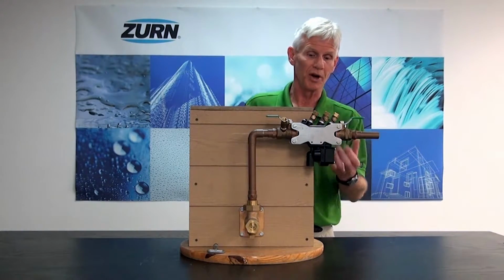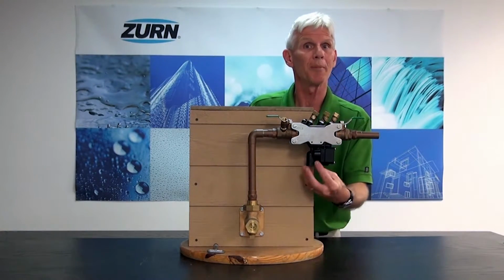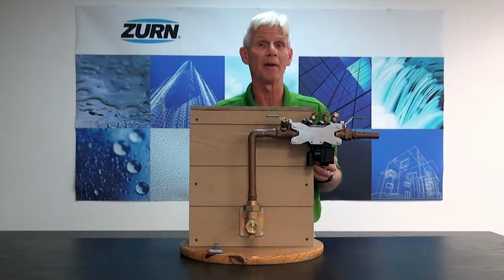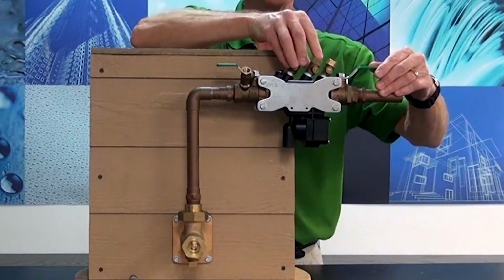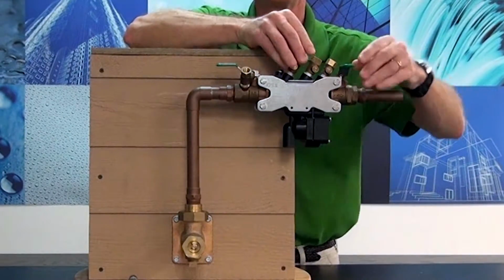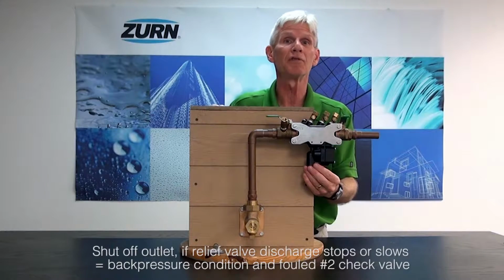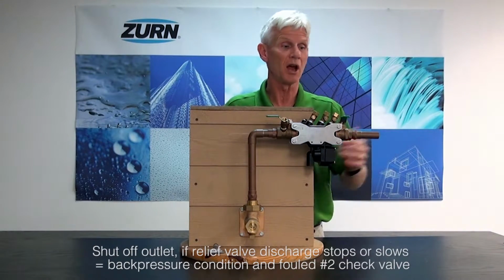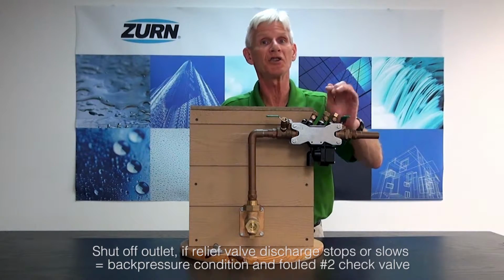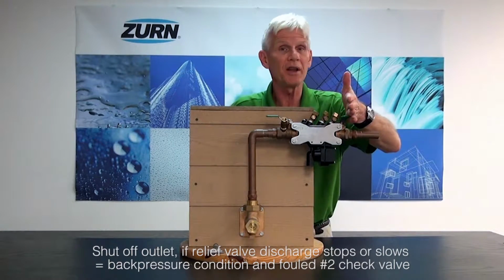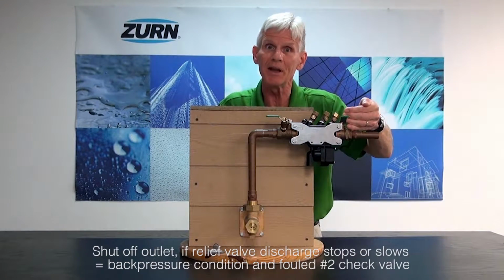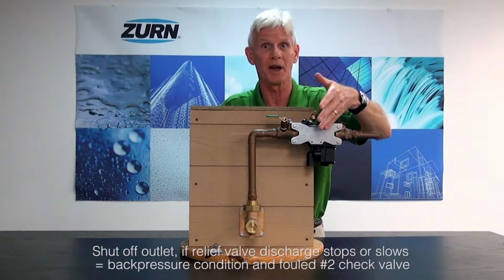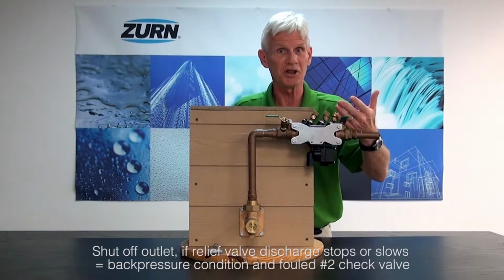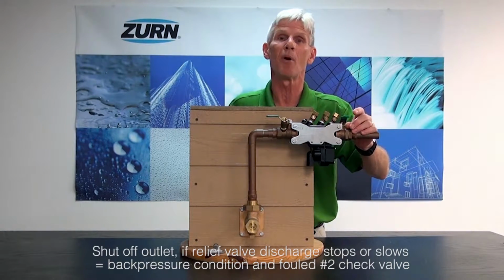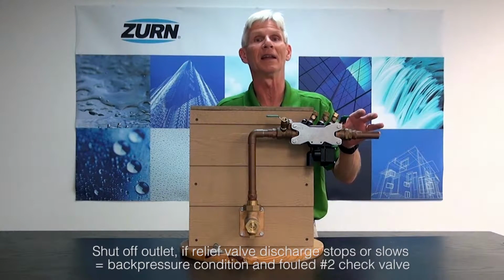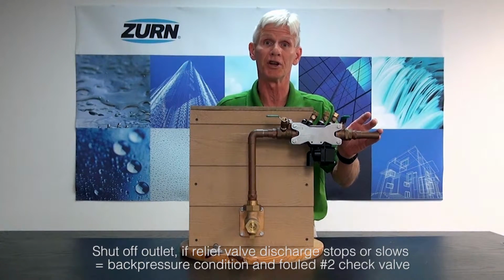So in essence, we walk up to this valve, we've got some discharge coming out of the relief valve, and we want to determine what's causing that. The first thing that we're going to do is shut off the outlet to the backflow preventer. When I shut off the outlet, if my relief valve discharge stops, what this tells me is I'm under a back pressure condition and my second check valve is leaking. By shutting that off, I'm preventing that back pressure from coming into the valve, leaking across the second check, and ultimately coming out of the relief valve. So again, if I see that discharge coming out, shut off the downstream ball valve. If the discharge stops, I have a leaking number 2 check valve and I'm under a back pressure condition.